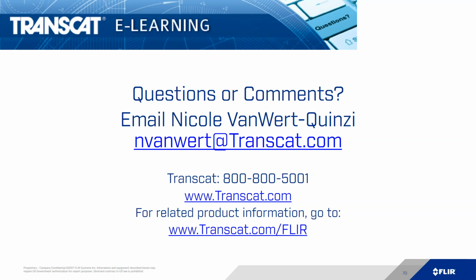Okay. One last question. We'll let this one slide through, and then you can do your review. At what distance is the IR camera typically calibrated at? We talked about calibration earlier with regards to when they calibrate the camera, they do it in a room, and they're about 5 to 10 feet away looking at a black body, so they can get the entire array of the camera on the black body.